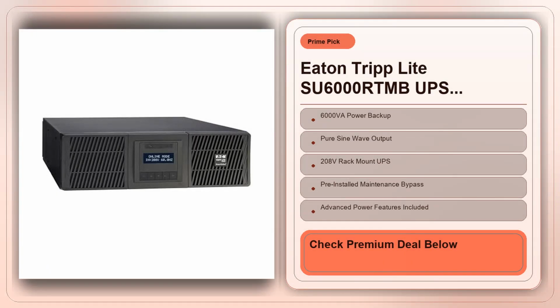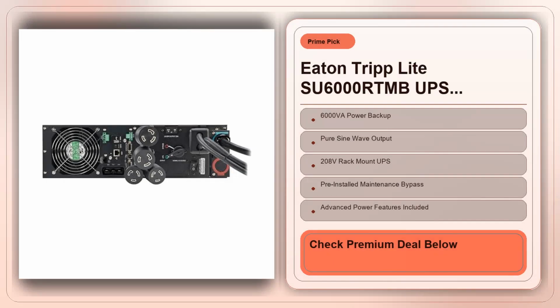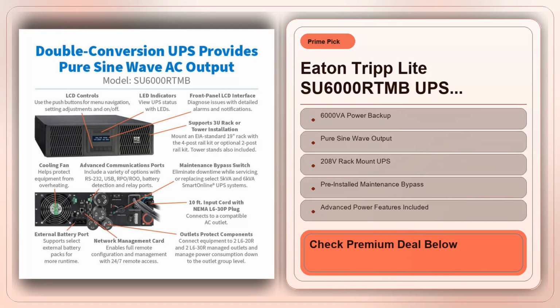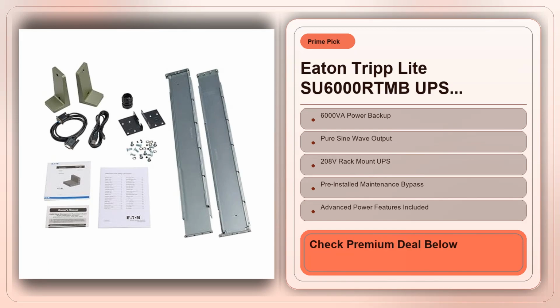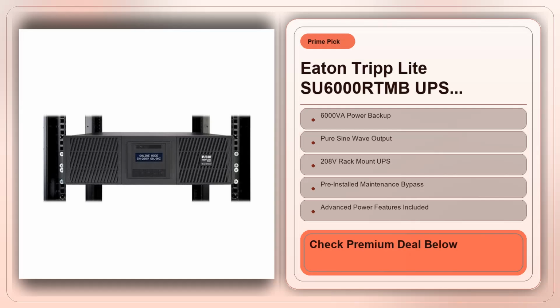With the SU6000RTMB, the bypass is built right in, so if you ever need to service your UPS or replace a failed battery, you can route power directly around the unit without pulling the plug on everything else. In a real-world rack where you might have a handful of switches, a storage array, and a small hypervisor all sharing that single UPS, that built-in bypass can mean the difference between a graceful switchover and a full-blown outage.